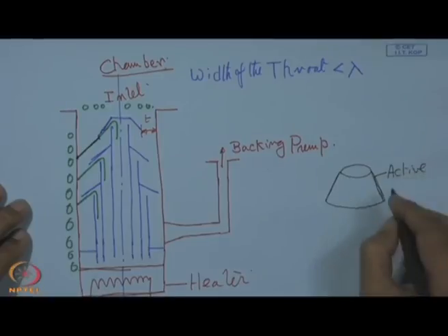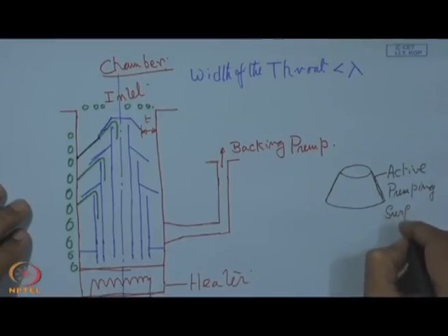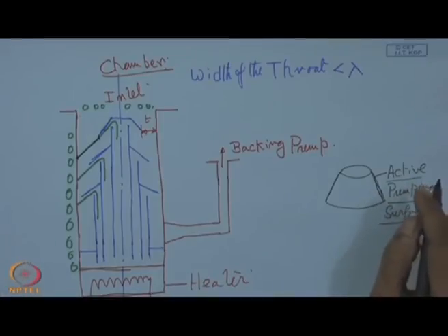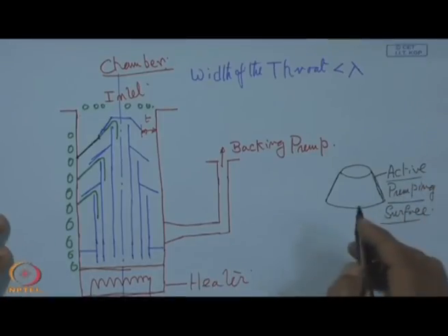For this pump, this conical surface, which is part of the cone, is actually the active pumping surface on which the gas particle is going to impinge.